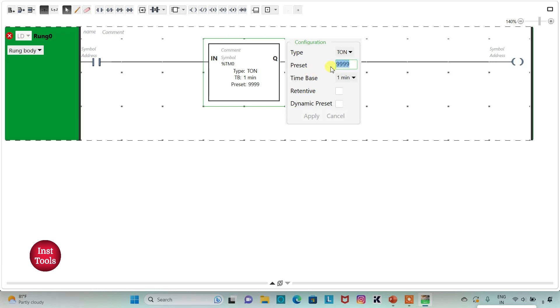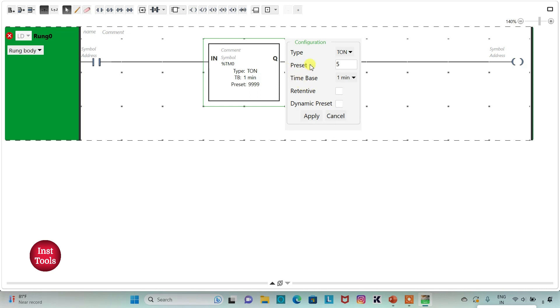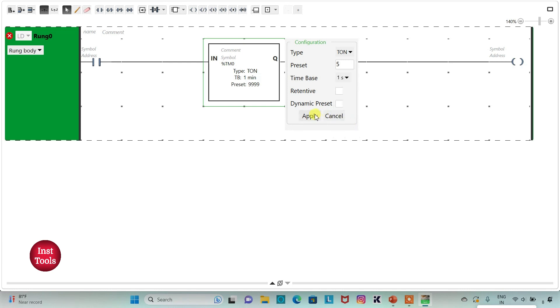Here I can set the preset value. For example, I will select it as 5. And then I will select the time base — for example, I can select 1 second. That is, I have set the preset value as 5 seconds. Or I can also change the time base — for example, 1 minute, so the preset value would be 5 minutes. I will keep it as 5 seconds, and then apply.